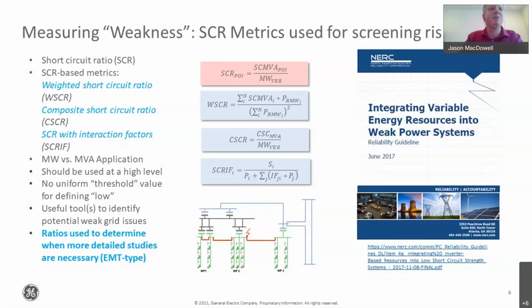And that will give an indication of how much inverter-based resource you have in a particular area, how weak it is, and what the limitations of the stability models are, and when you might need to go deeper and use the transient models. Traditionally, if that ratio was below about 3, we said let's go deeper and do the assessment with the EMT models. That threshold continues to get lower and lower, and as the models get better, they will ultimately be allowed to go a little bit lower, to 2 or even 1.